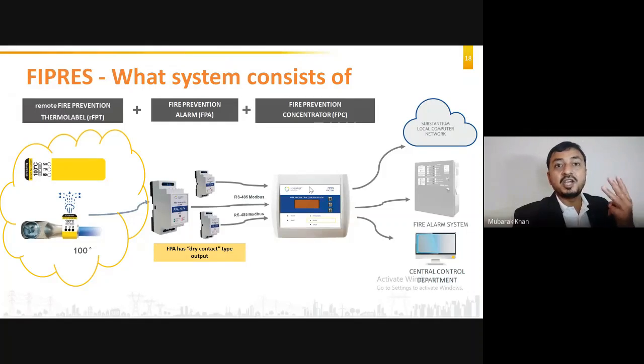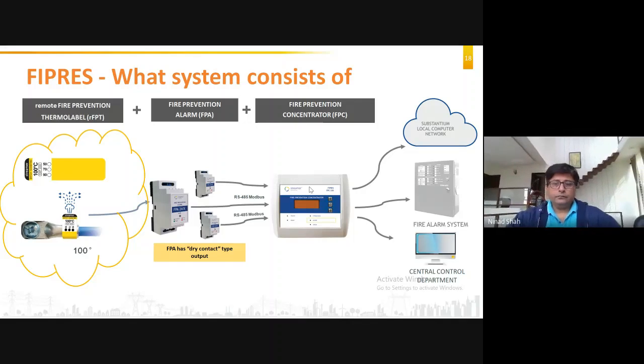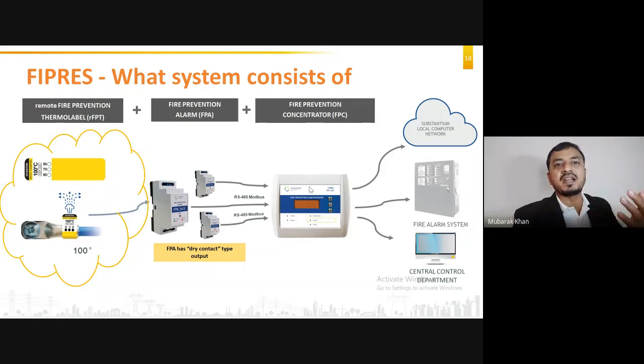Third reason: during operation and maintenance, when operators open the joint and close it, they don't tighten it with the tightening torque. We are all electrical engineers—let me know how many electrical engineers have torque spanners with them. Normally they just tighten it by hand. Even in the factory they may use torque spanners, but at the site, do you think they use a tightening torque spanner? Very rare, very difficult, right? So if maintenance is implemented in the best manner, faults will come very late, or maybe not at all. But the pity is we don't do it in the perfect way.